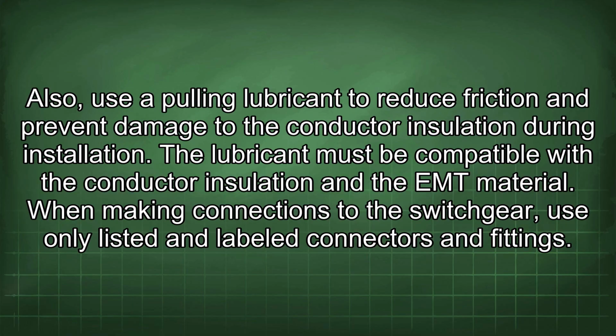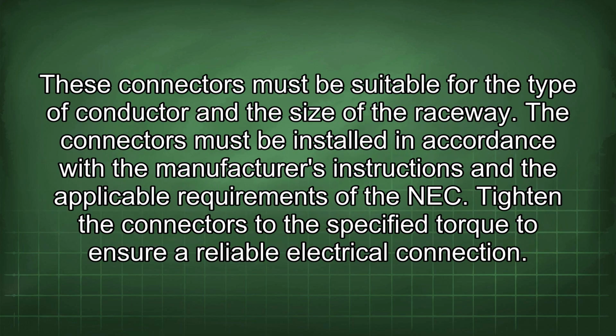When making connections to the switchgear, use only listed and labeled connectors and fittings. These connectors must be suitable for the type of conductor and the size of the raceway. The connectors must be installed in accordance with the manufacturer's instructions and the applicable requirements of the NEC. Tighten the connectors to the specified torque to ensure a reliable electrical connection.